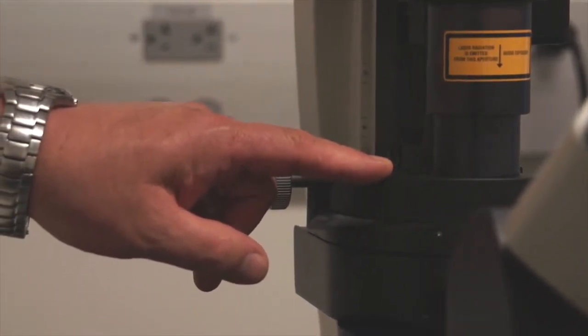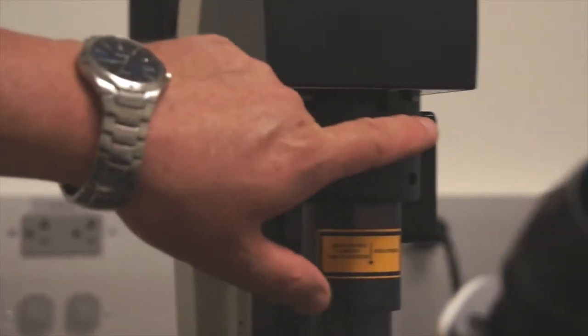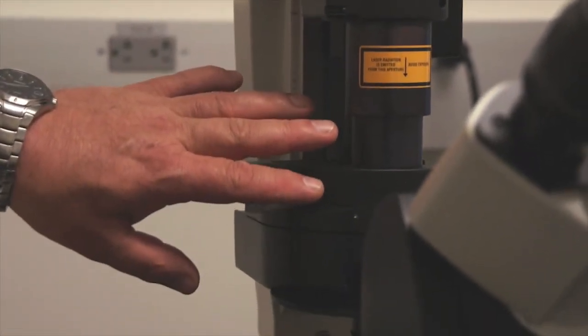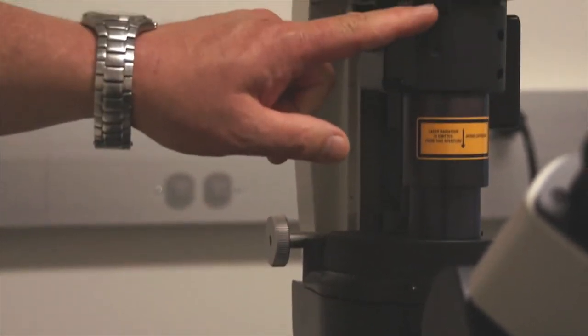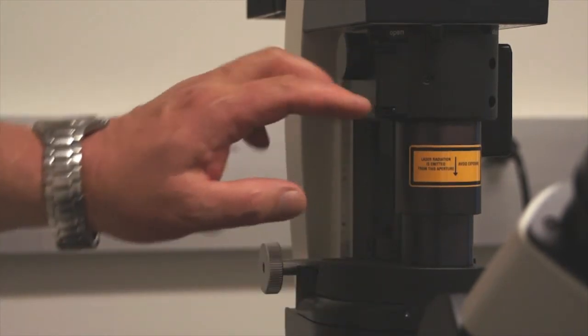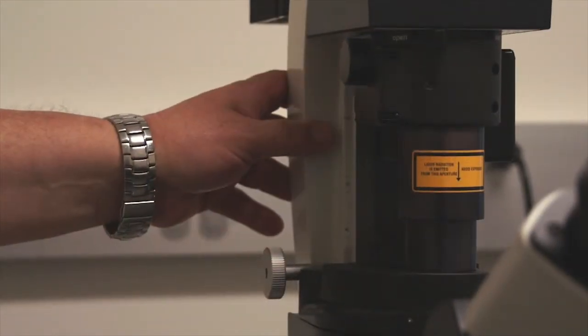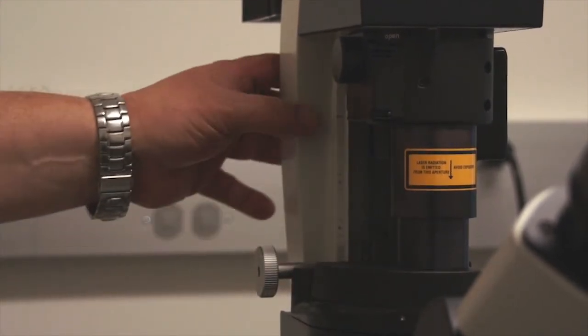And so the field diaphragm on this microscope is manual and it's located here. And so we would close this down and open it up so that we could see it in our field of view. And so we're going to discuss condenser alignment specifically as we did on the upright compound microscope, aligning the condenser, closing the field diaphragm, and then using the alignment tools in here to align the field diaphragm to the field of view.